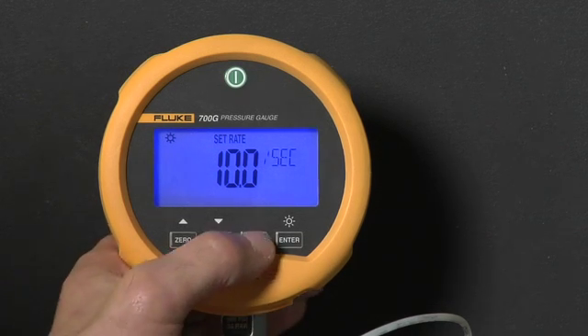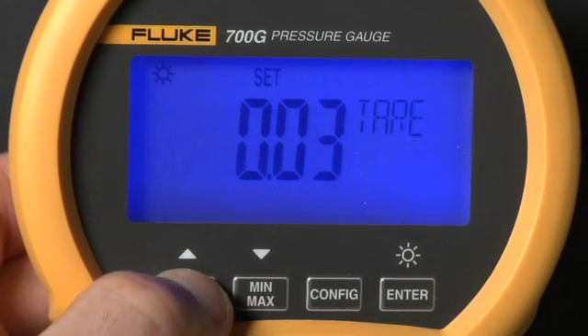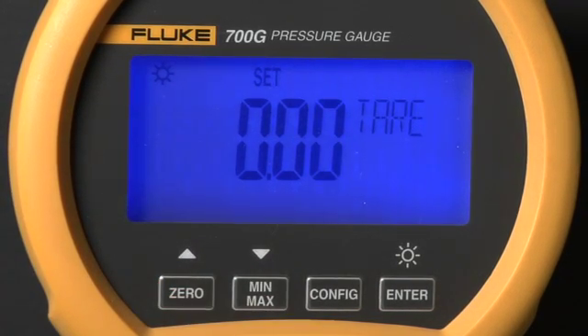Press config again to set a tare value with the up and down arrows, which offsets the measurement by the set value. Tare is often used to zero out the display with a measured pressure value, so you can view changes in pressure from the set value.